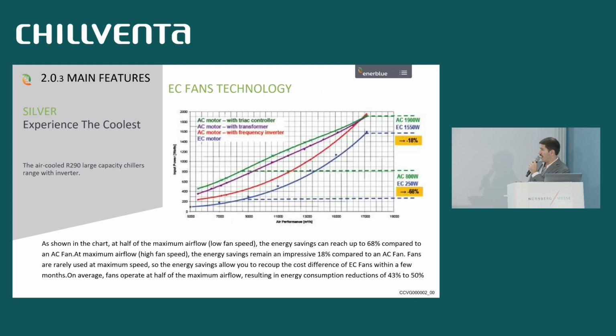EC fans are standard for our chillers. EC fans not only make our unit more efficient and compliant to the norm, but they allow the plant to save more or less 20% of the energy absorption compared to AC fans.